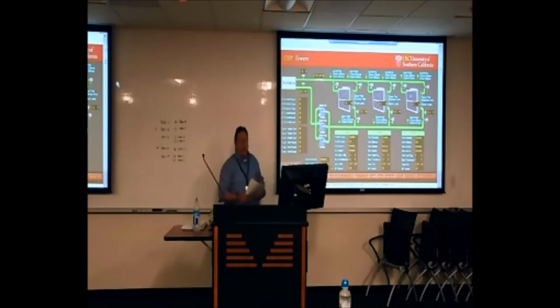And one thing I want to point out, it looks like it's trapped by virtue of where it is. There's a catwalk above it, and it's almost right up against it, so the sensor cannot be extracted, but it's where it had to go. It's the only place it could go. So there's a couple of bolts on the catwalk where you can take sections out, and that's how it was installed. The section of the catwalk was removed, sensor was dropped in, and then the catwalk section was put back. So if there's ever a need to replace that sensor, that's how it would have to come out again. So again, just extract that section of the catwalk to have access to that sensor to pull it out of its stilling well to replace it.